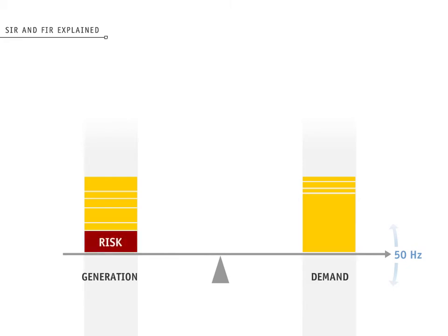The risk or risk setter is the single generator that's contributing the most power. The risk setter in either island can also be the HVDC link. For our purposes here, the HVDC is represented as a generator injecting power into the system. If we schedule enough reserve to cover the loss of the risk setter, then we will definitely have enough reserves to cover the sudden loss of any smaller generator.